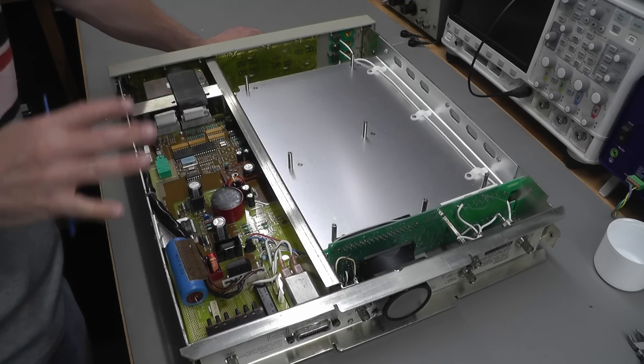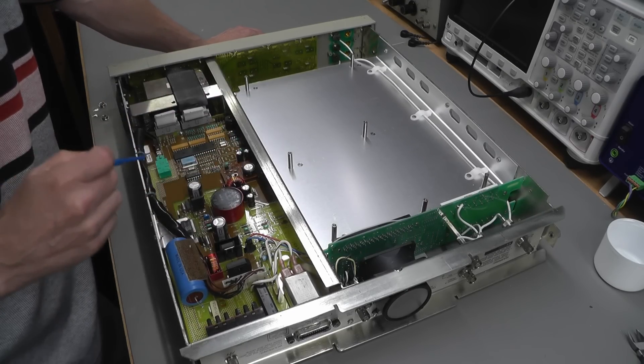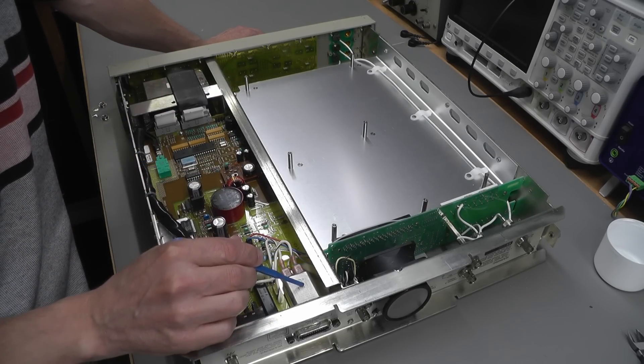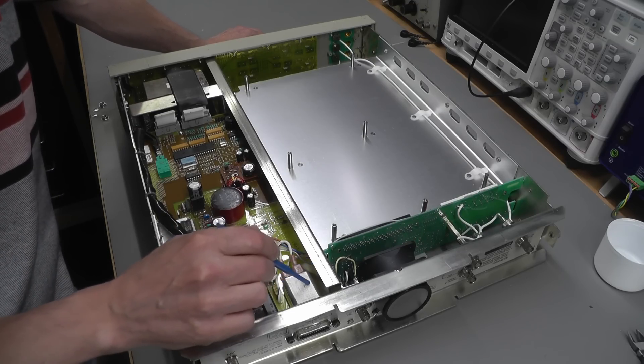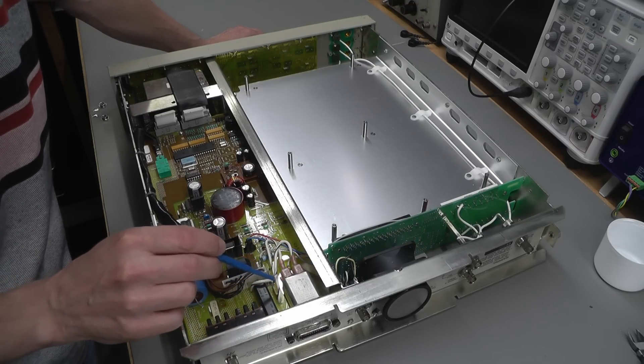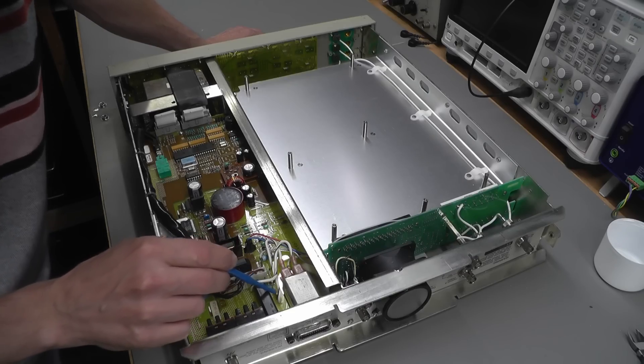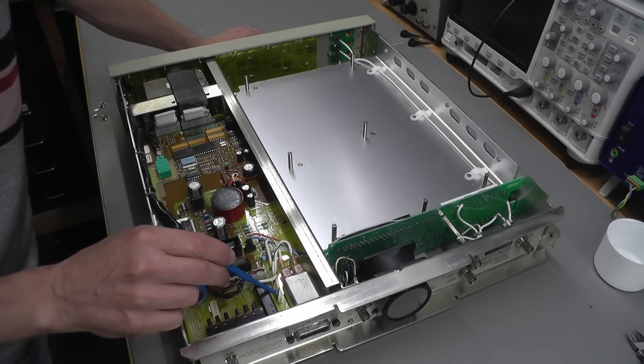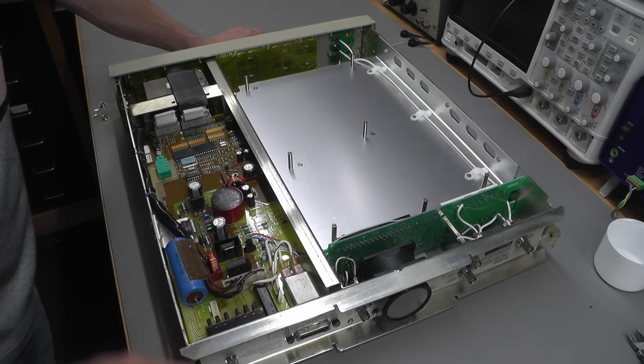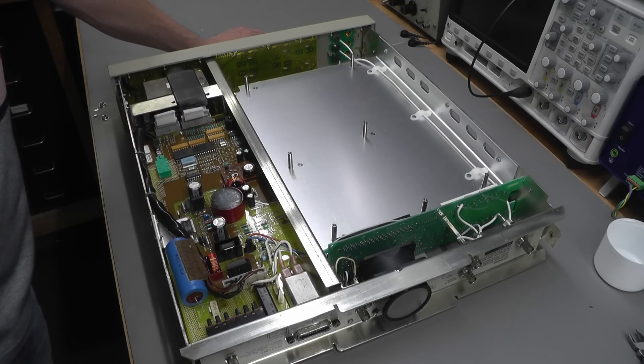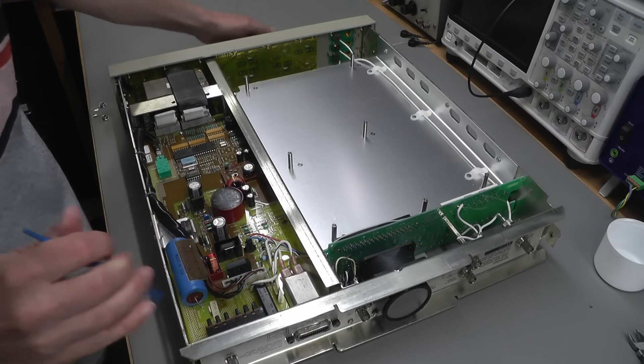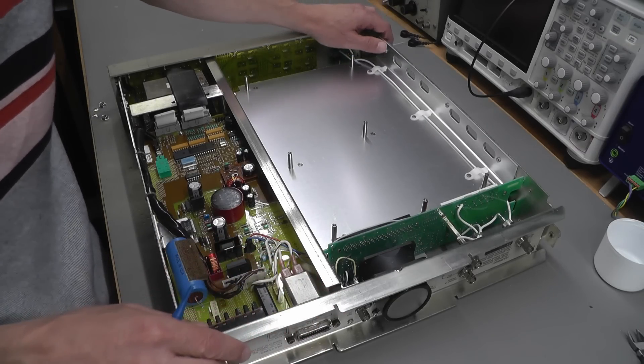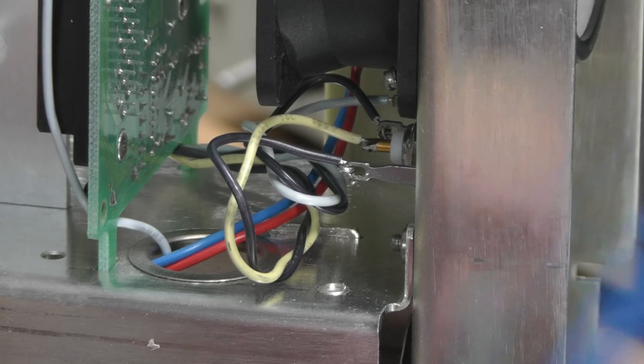Well, this is the underside of the unit. There are some parts here I will be replacing, starting off with the line filter—it's got a Schaffner line filter. I will be changing out that. Right next to that there's a small Rifa capacitor there, not sure if that's an X-class or what, but I'll be changing that out. And there's a few electrolytic caps—I'm going to recap this power supply.